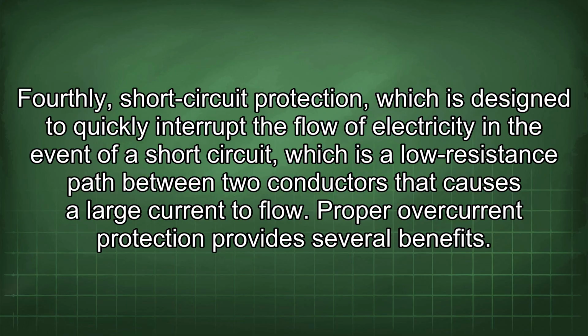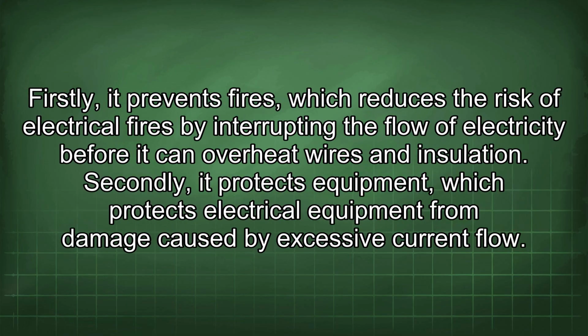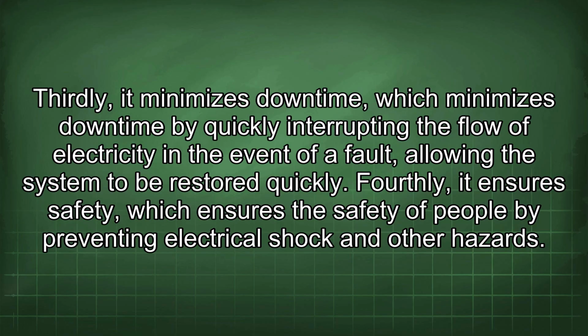Proper overcurrent protection provides several benefits. Firstly, it prevents fires, which reduces the risk of electrical fires by interrupting the flow of electricity before it can overheat wires and insulation. Secondly, it protects equipment from damage caused by excessive current flow. Thirdly, it minimizes downtime by quickly interrupting the flow of electricity in the event of a fault, allowing the system to be restored quickly. Fourthly, it ensures safety, which ensures the safety of people by preventing electrical shock and other hazards.